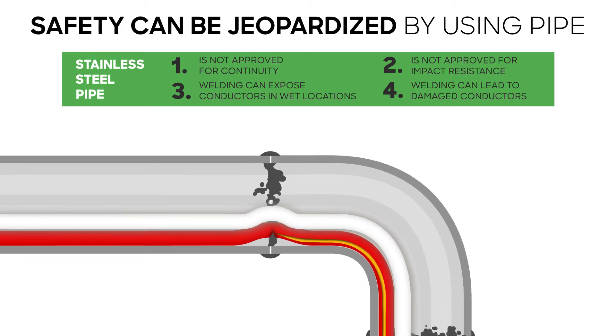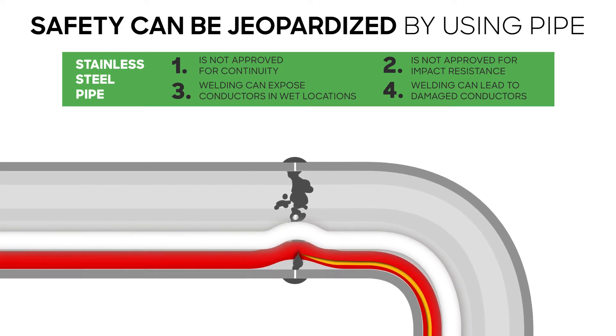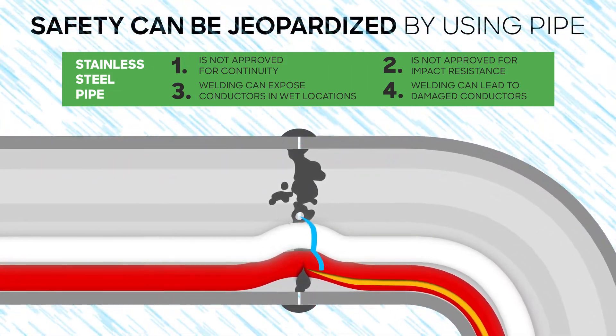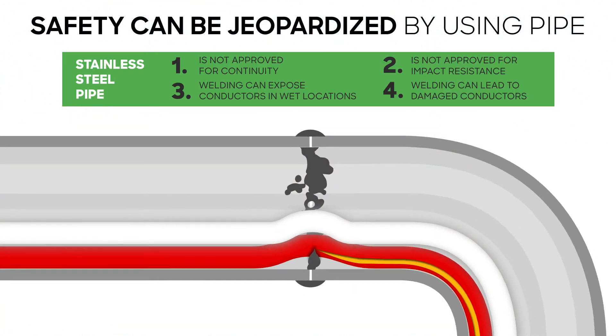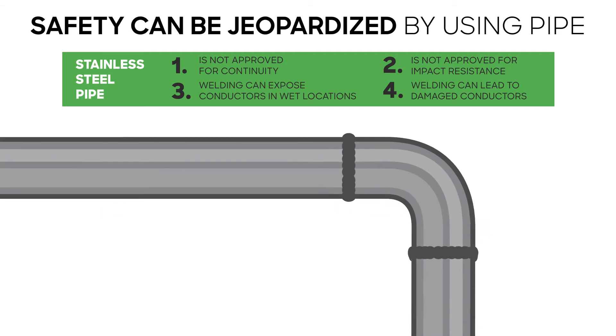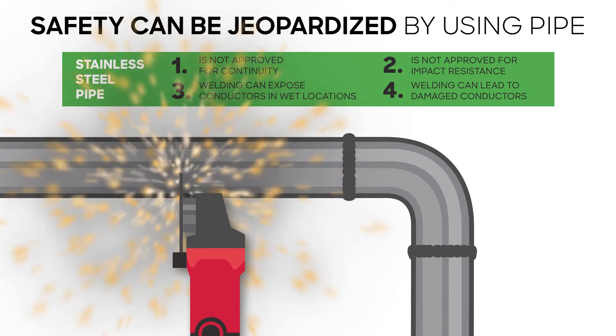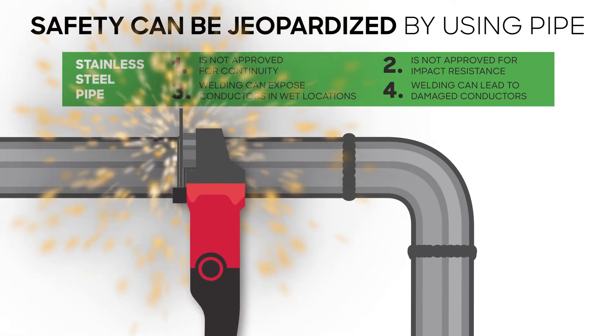It is also very difficult to inspect whether a weld is completely sealed. If the raceway is installed in a wash-down environment, it is possible for liquid to enter and short out any exposed damaged wire. If an installation requires adding a new machine and more cable to the raceway and you have used welded pipe, you've welded the system shut instead of using UL-listed fittings. It all adds up to more cutting and welding, more cost, more violations, and more risk of exposed wire.